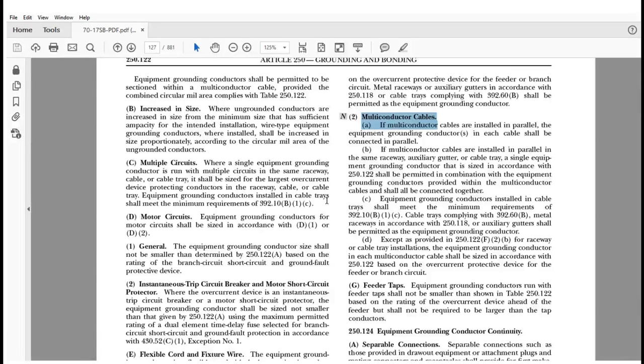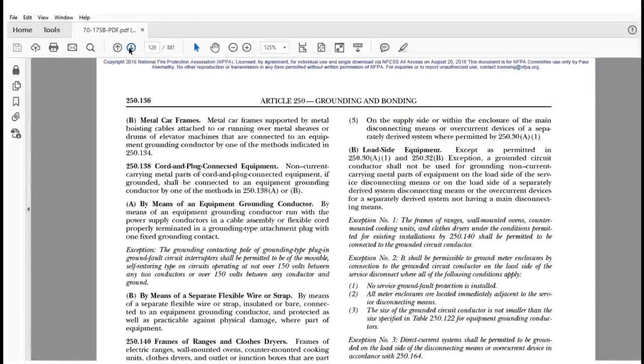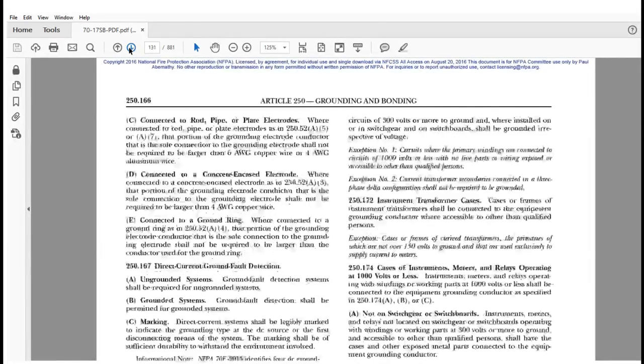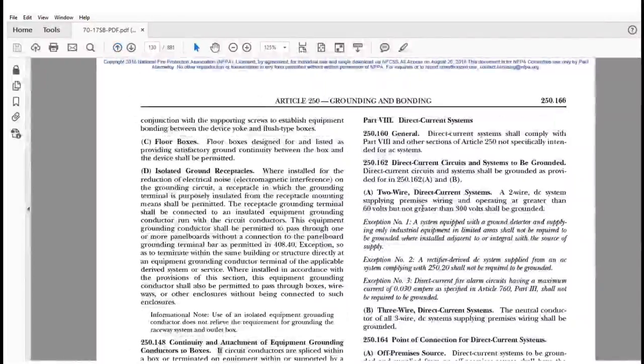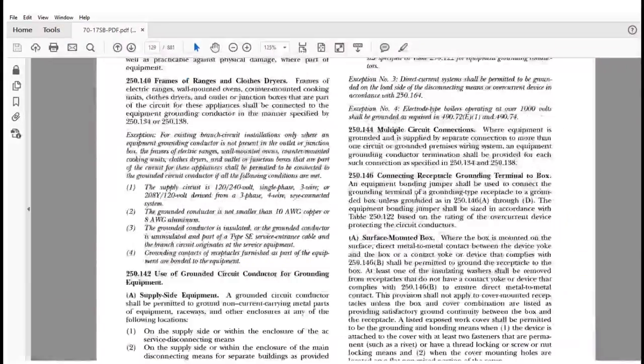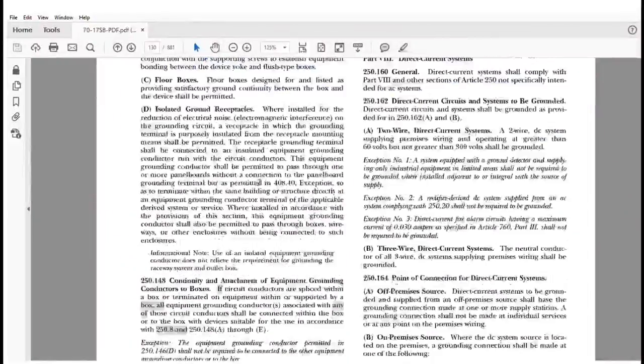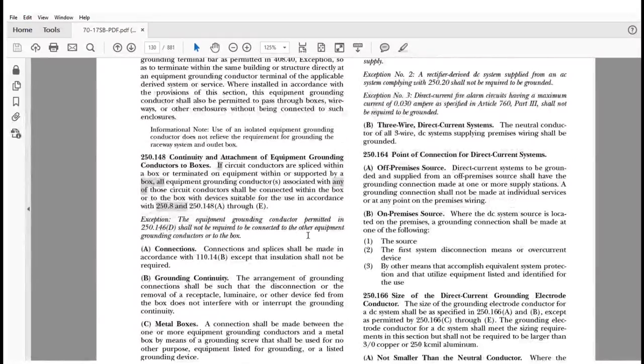All right, next one we're going to look at is 250.148. This is the continuity and attachment of equipment grounding conductors to boxes. So let's go to 250.148 and look at that change. And we're getting close to the end, so hang in there with me. If you zoned out on me, we're getting close to the series end, so it doesn't look like we're going to go more than about an hour and 30 minutes, so that is great. Hopefully you've written all this down, all these changes, so you can go look back.